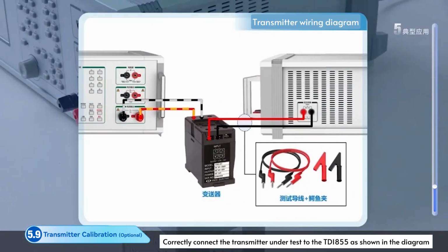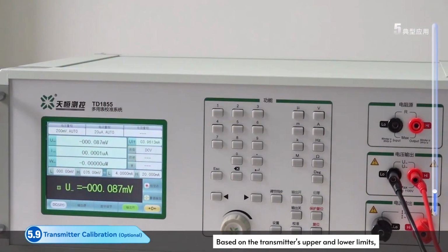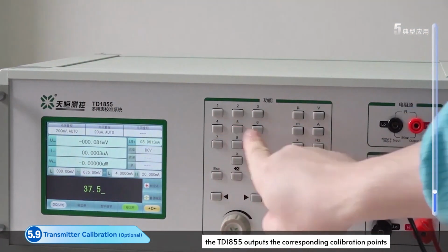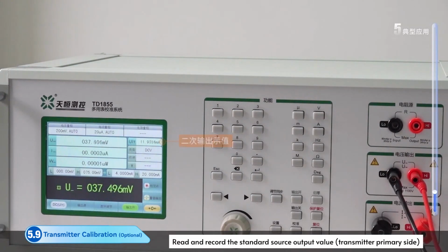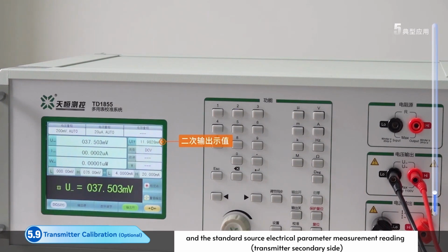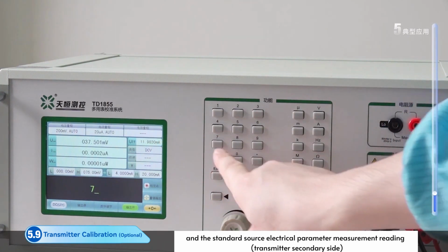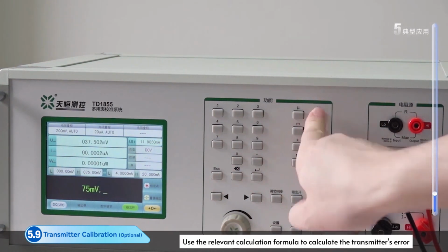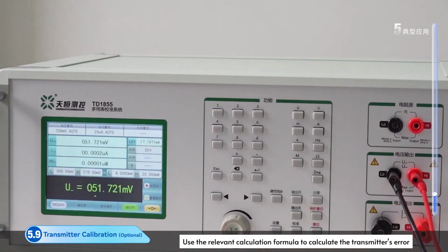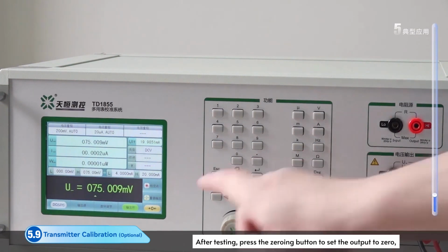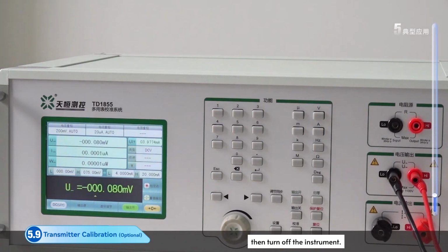Correctly connect the transmitter to the TD1855. Based on the transmitter's limits, the TD1855 outputs the corresponding calibration points. Read and record the standard source output value and the standard source electrical parameter measurement reading. Use the relevant calculation formula to calculate the transmitter's error. After testing, press the zeroing button to set the output to 0. Then turn off the instrument.